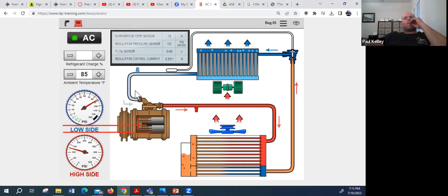Interesting. Alright, and so if we look at this, our high side is not really getting that high and it's fluctuating, and our low side is not really getting that low and it's fluctuating. That's kind of interesting. And yes, when there's air in the system, it can do a little bit on the low side, but usually it's much more noticeable on the high.